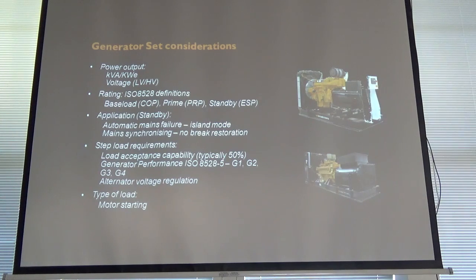Okay, now there are different market sectors here. There are construction side, and there are also data centres. So there is a special rating that's given for data centres, which relates to a COP, because in the context of data centres, their N+2, 2N or aspects related to that site, the surety of power, what they'll do is often they'll take a prime rated power unit and rate it as a continuous COP unit for a data centre application. So there are exceptions to this.